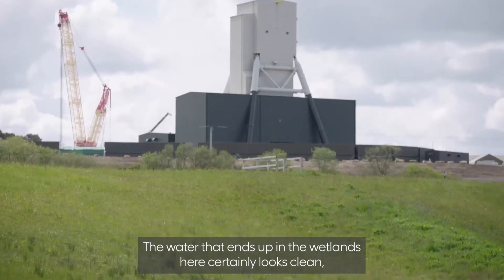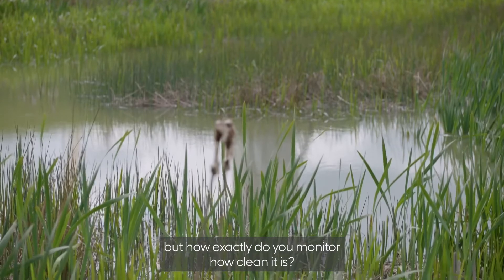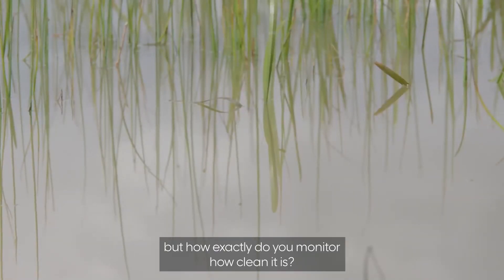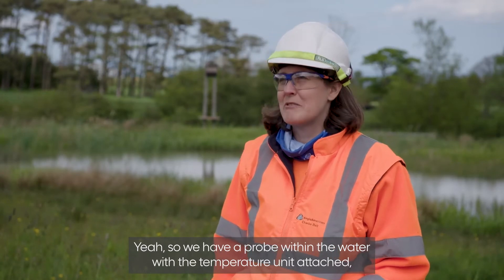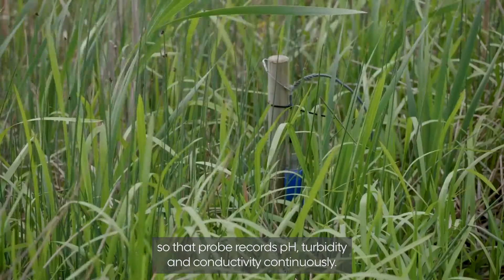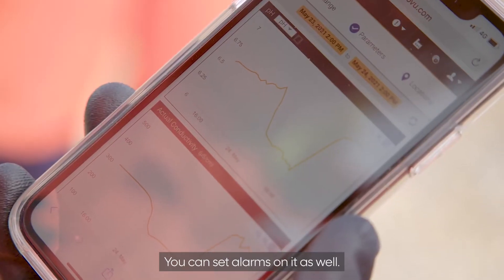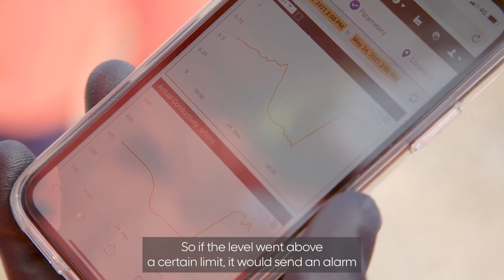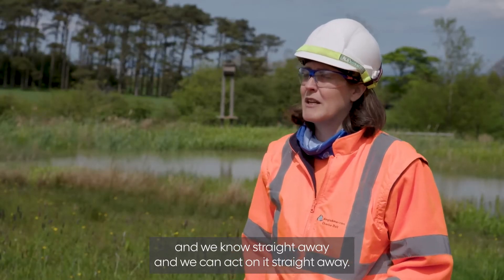The water that ends up in the wetlands certainly looks clean, but how exactly do you monitor how clean it is? We have a probe within the water with a temperature unit attached. That probe records pH, turbidity, and conductivity continuously. We can set alarms on it as well — if a level went above a certain limit, it would send an alarm and we'd know and act on it straight away.